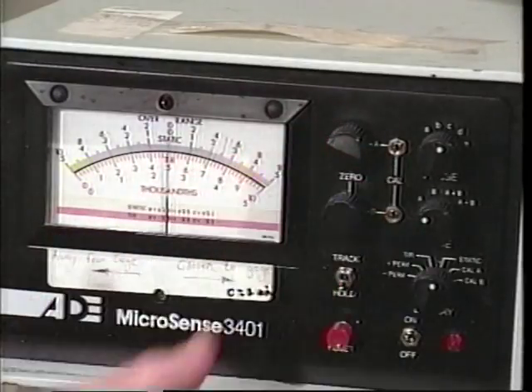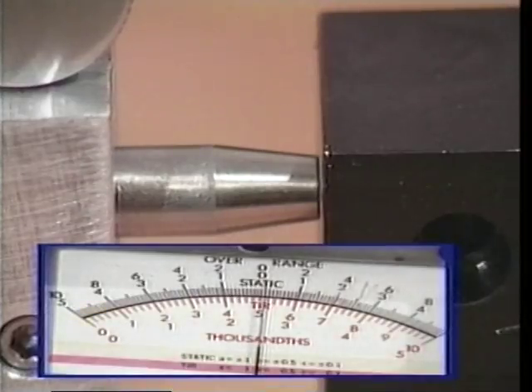If another range is desired, switch to that range, and if necessary, use the electronic fine adjust knob to re-zero the display. The separation of the target surface and probe tip may now be varied with the variation being displayed by the cap gauge meter or the analog voltage output.